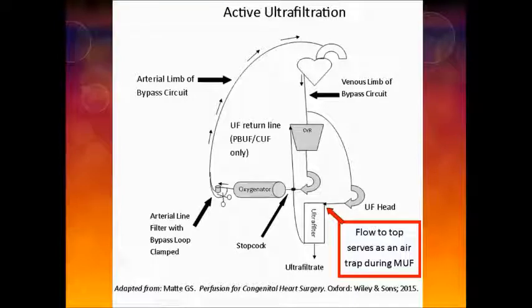This diagram shows an exclusively active ultrafiltration setup for all types of ultrafiltration. Here, there is a pump head which always sources blood from the venous line. It pumps blood to the top of the hemoconcentrator, and that blood then exits the bottom and can go back to either the reservoir or to the pump boot line. The return is to the reservoir for pre-bypass ultrafiltration and active ultrafiltration during bypass. It is to the pump boot line during our method of MUF, or modified ultrafiltration.